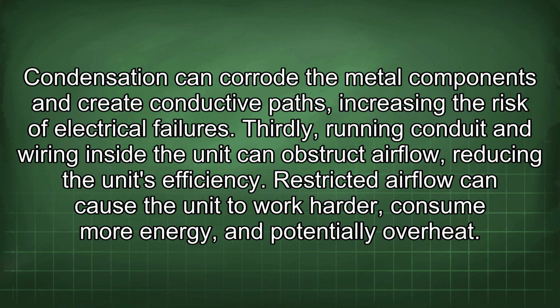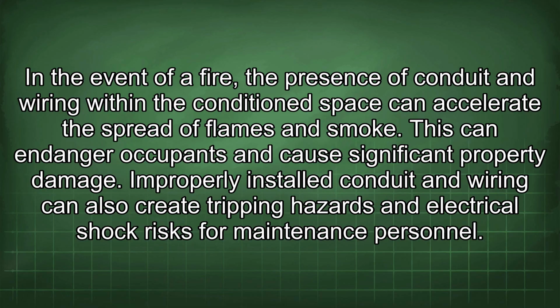Thirdly, running conduit and wiring inside the unit can obstruct airflow, reducing the unit's efficiency. Restricted airflow can cause the unit to work harder, consume more energy, and potentially overheat. In the event of a fire, the presence of conduit and wiring within the conditioned space can accelerate the spread of flames and smoke. This can endanger occupants and cause significant property damage.